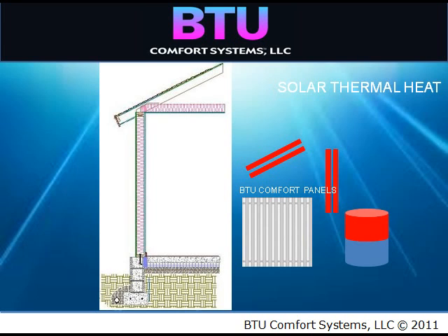Depending on the building's orientation, the number of panels, and your storage capacity, you can capture varying levels of thermal heat for use right then and there, or for use later on in the day. In a sister company, Radiant Design, I've done some solar systems where we've captured the heat during the day, stored it, and then utilized it at night to shut the boiler down. Doing so saves about 40 to 50% on the fossil fuel use.